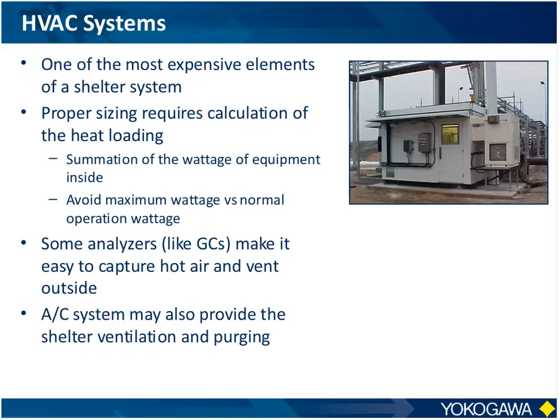And also, since the air conditioner has a blower system and such, if you're going to have one of those, it also makes it not much more difficult and not much more expensive to add a full purging system and ventilation system to the entire shelter. For example, you can see that on the picture there, where you see this big gray stack going out above the air conditioner, where it extends up, let's say 25 feet in the air, where it's known that you'll have safe air to bring in, to keep the entire shelter purged and ventilated.